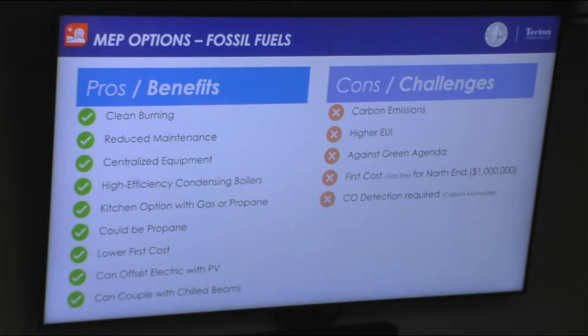Yes, you have a million dollars as a line item in the original project budget. We did an analysis, shared it with the CMR, and it was validated by Mark. On a past project needing a gas line of similar distance—this one is about 2,900 linear feet, validated by our civil engineer—we used $250 per linear foot for budgeting. For this exercise, doing the math, it comes out to about $275 since that project has finished construction.